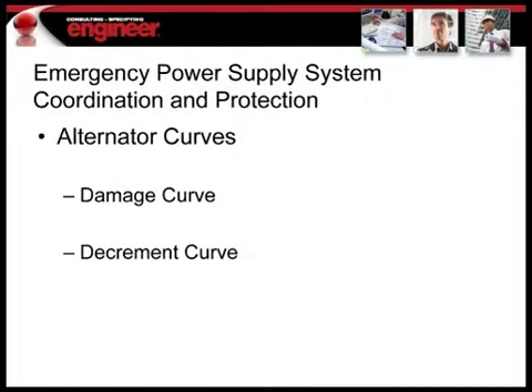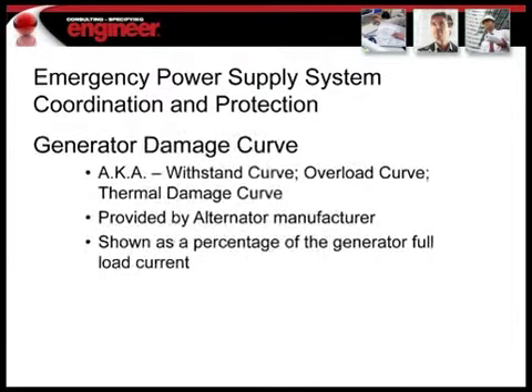There are two curves that are important when you take a look at coordination with the generator: the damage curve and the decrement curve. The damage curve is the first one we'll look at. There are a lot of different names for it. You can call it the withstand curve, the overload curve, the thermal damage curve. This curve is available from the manufacturers. When you get the alternator data sheet, typically you can ask for this information. The damage and the decrement curves are both available from the manufacturer, and then you have to model it and coordinate around it. So they can provide it.